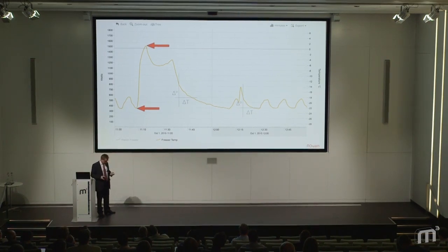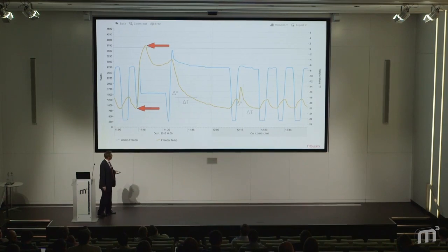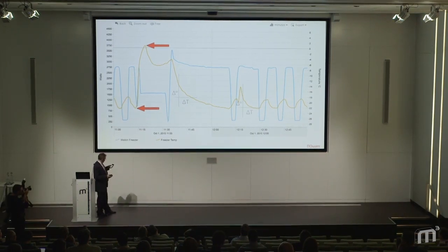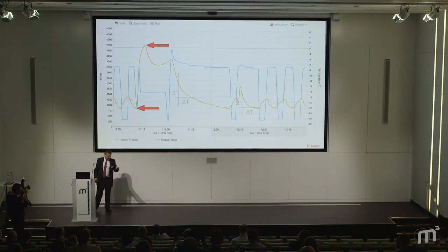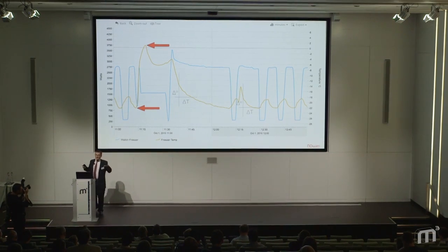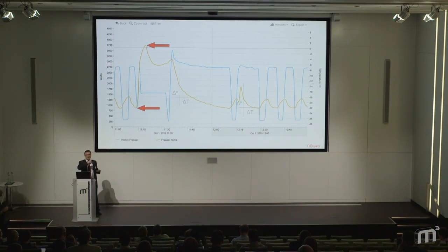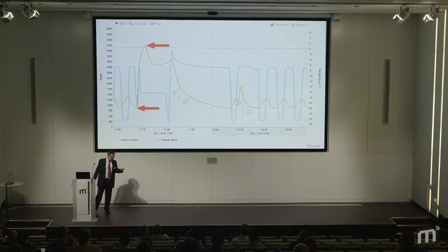Context is also important, of course. The relationship between sensors is more telling than any metric in isolation. Deriving rate of change with respect to, say, the compressor running is going to give us another level of isolation. This will mean that this becomes much more consistent amongst lots of that particular type of appliance but eliminates things like the weather and the loading and the installation.